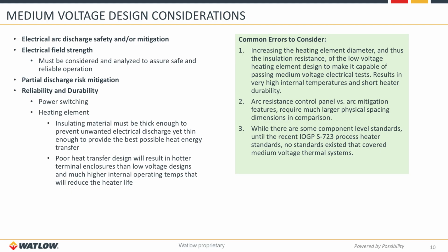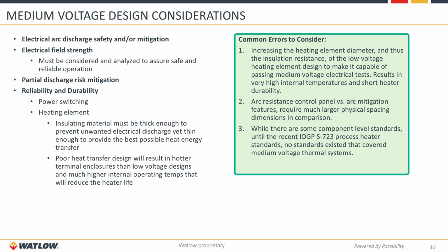For heating elements, we need to make sure that the insulating material is thick enough to prevent any unwanted electric discharge, yet thin enough to provide the best possible energy transfer. In other words, balancing insulation thickness for safety versus heat transfer efficiency. A second consideration is managing terminal enclosure temperatures to enhance product life and durability. On the right side here, I'll cover some common errors to consider, which are simply oversizing low voltage element designs that can result in high internal temperatures and rapid durability loss.